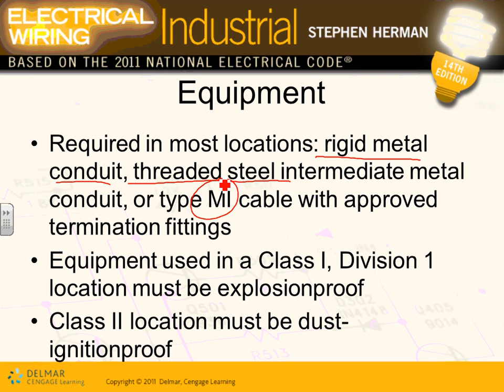Equipment. If you're using equipment in a Class 1, Div 1 location, it has to be explosion-proof equipment. Now, what is explosion-proof equipment? If you get this picture in a Class 1, Div 1 location, it has to be explosion-proof, meaning, number one, the operating temperature of it will not exceed the igniting temperature for the gas. Number two, it wouldn't allow the gas to get into it. Number three, if the gas got into it and had an explosion inside it, it will contain that explosion and would not spread it all over.